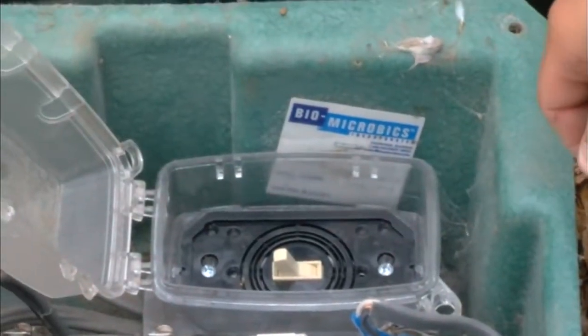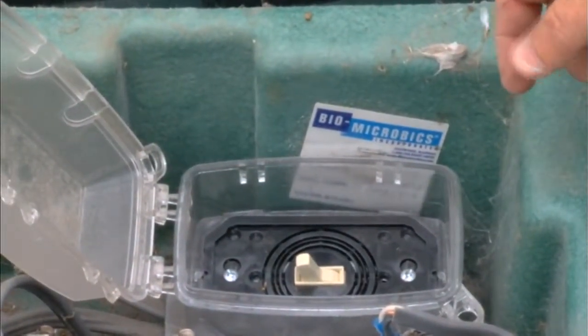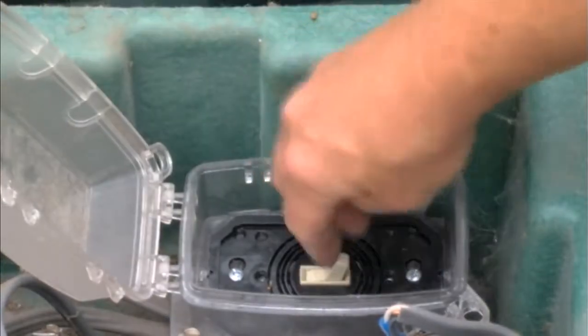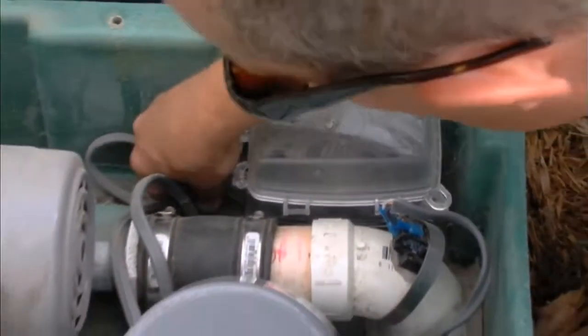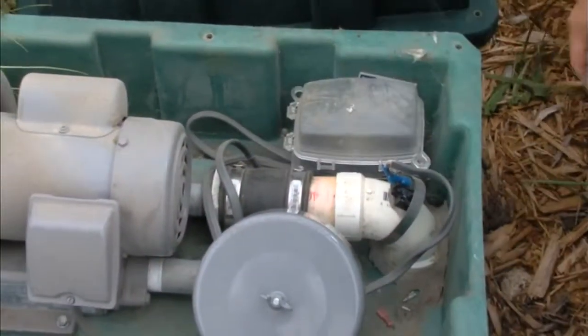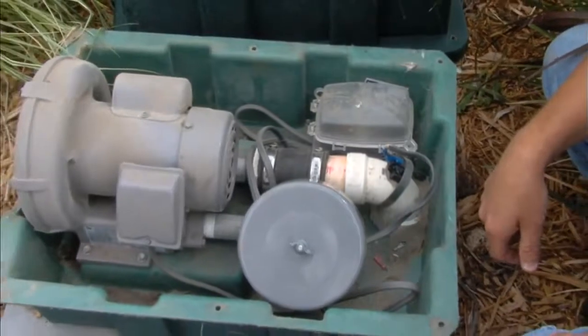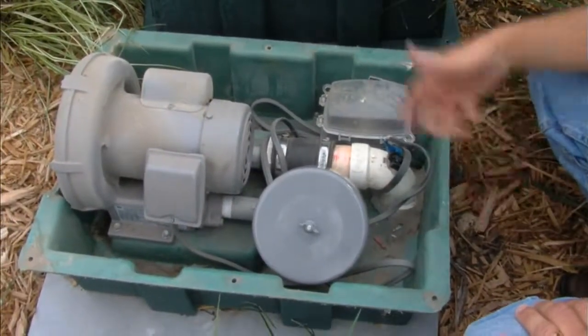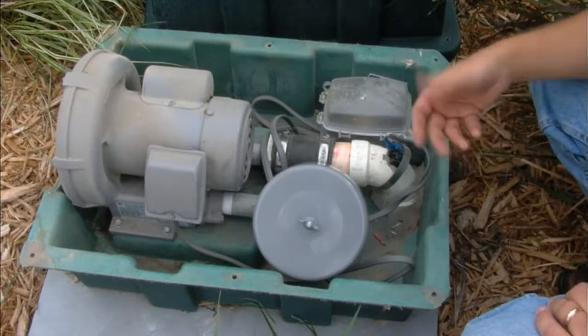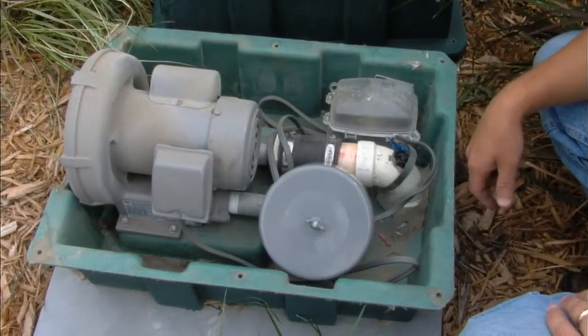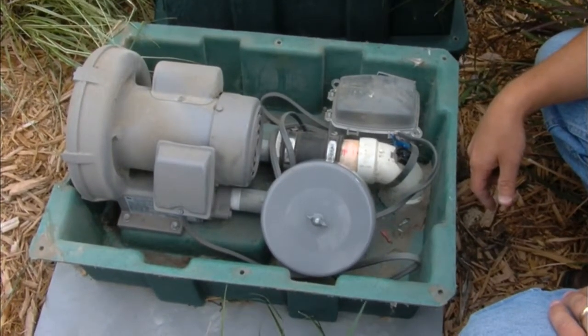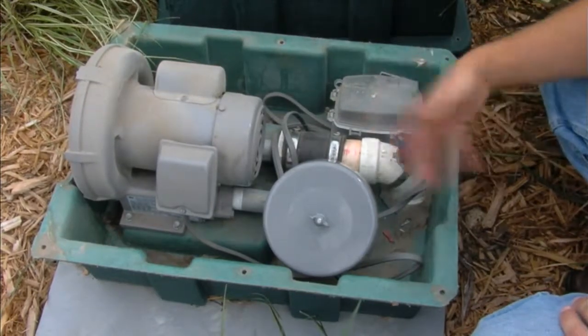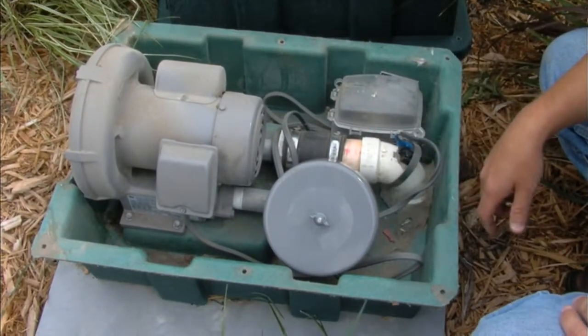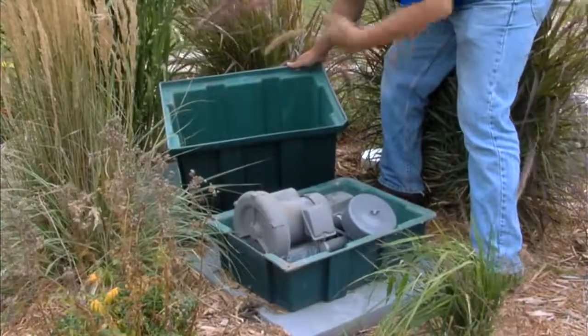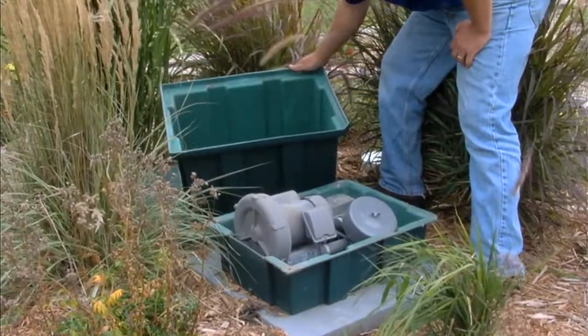If you have a disconnect at the blower, you're going to want to check and make sure that that's doing okay too. Obviously make sure it operates correctly. Close that back up, take a look at your electrical connection, make sure the disconnect's mounted in there correctly and well. And then last but not least, check your blower housing to make sure there's not any debris brought in by mice or other creatures, let's say, spiders, that sort of thing. If there is any debris in there, make sure you clear it out so it's not going to cause any problems in the future.